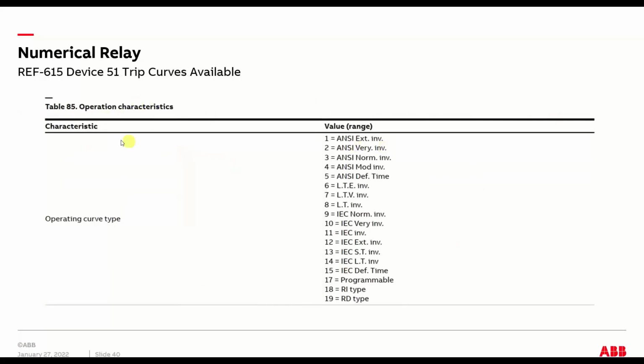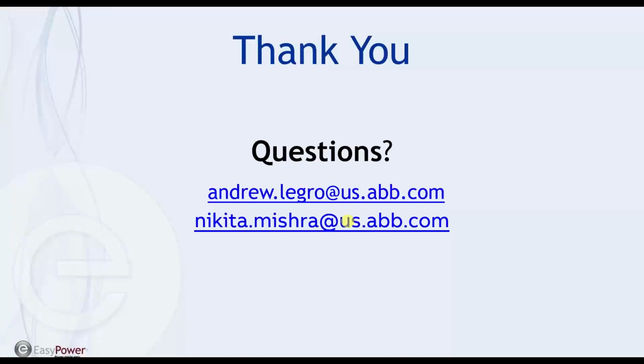And then here, lastly, I think it's the last slide. This is an example. I pulled up one of the ranges of our relays in terms of what curves you can select. So you've got a whole slew of stuff. You've got all your ANSI from extremely inverse down to definite time. I don't even know what LTE inverse is. Honestly, I can't tell you what some of this stuff is. Then your IEC curves, which is the European standard, and the same thing. You've got all your inverse type things. Programmable, you can actually go in and program basically your own curve in the relay. So it's got essentially infinite flexibility on developing the kind of curve that you need for your specific protection.